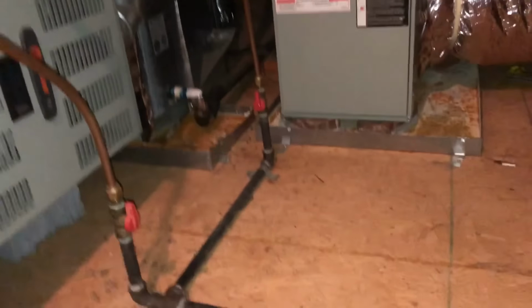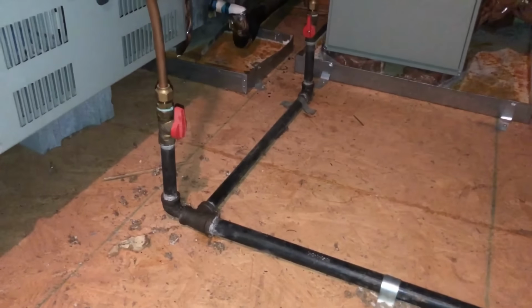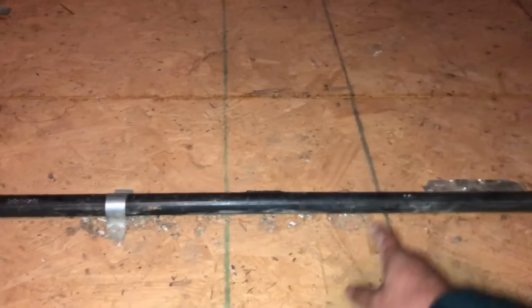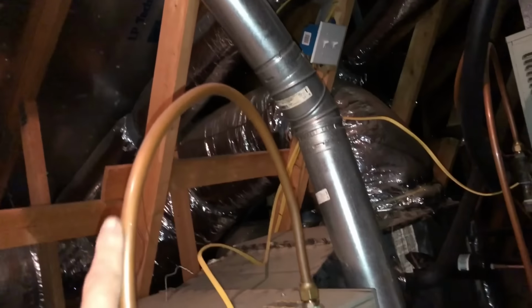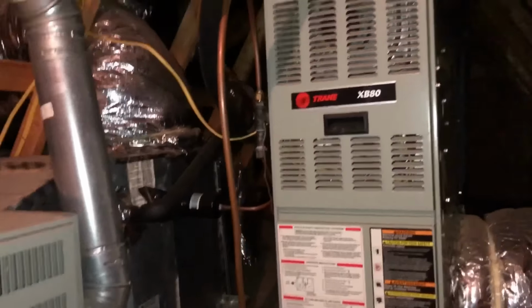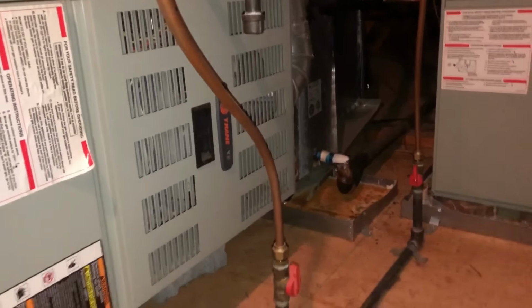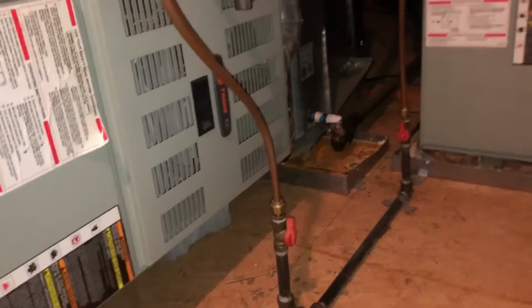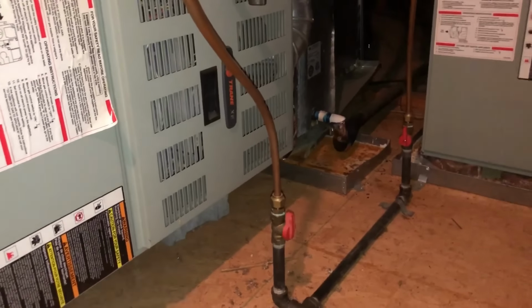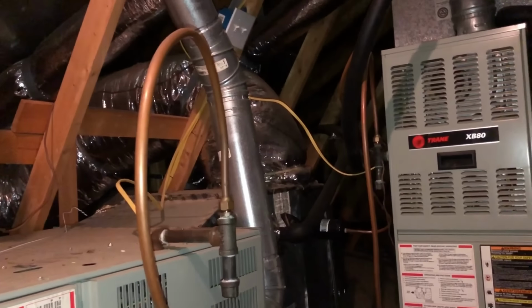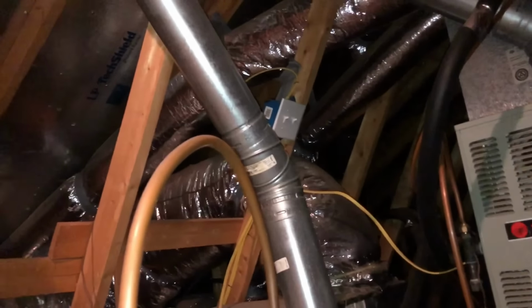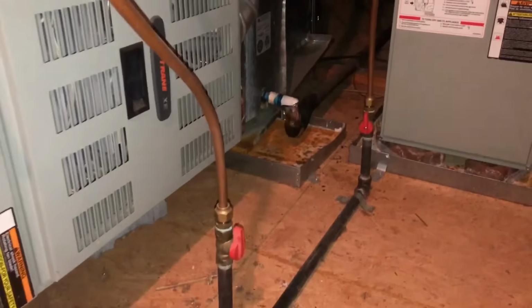Okay. Now I know that you northern guys and you guys that work for union and everything, you're going to say, why in the world would you go through the trouble to run nice black iron pipe, clamp it down to the platform, make it look neat, and then turn around and loop that big ugly loop of copper going right in the top? And there's another big loop on that one over there. Well, that's actually legal here. You can have up to 6 foot of either flexible line or copper or range connectors, whatever you want to call those, flex hose connectors. They can be up to 6 foot between the appliance and the shutoff.